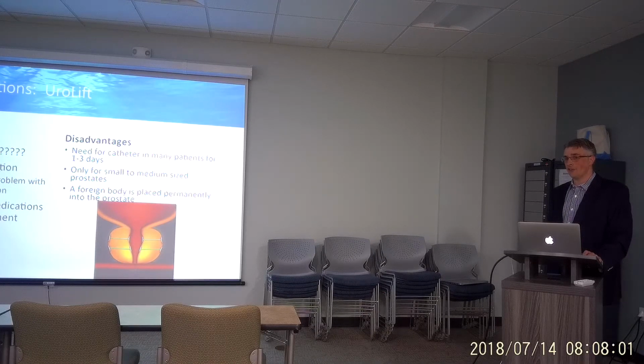There was a thing out there, if anybody's heard of it, done in the late 1990s called a Urolume, which is a stent, which on the surface of things makes a lot of sense. We put stents to unblock somebody's arteries in their hearts all the time. Been doing that for decades with good success. Well, why not just do it for the prostate? Well, the calcium levels in our blood is about 9.5. The calcium levels in your urine are 200. So over time, those stents calcify. The UroLift is coated with a substance that eludes calcifications.